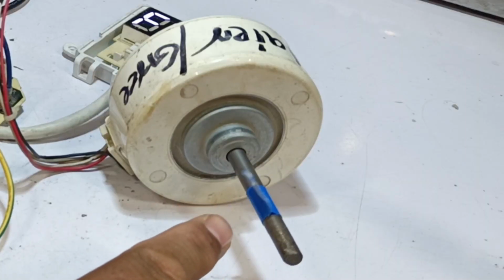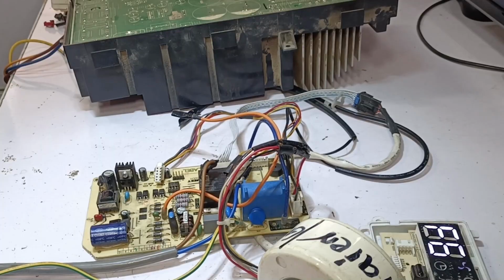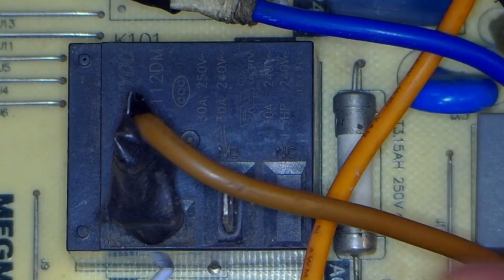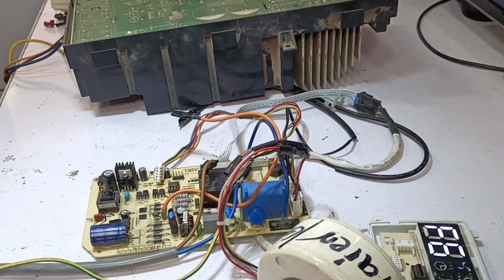Normally, the unit is installed above, and we don't understand why the F6 error is appearing. Sometimes we assume that the outdoor PCB is faulty or the wiring is damaged. Now look, as soon as the fan motor stopped, it started showing the F6 error. What's happening here is that the switching relay is not turning on under any circumstances. Someone has already worked on this PCB before, but the issue was not fixed. Now, since the relay is not turning on, it is not supplying power to the outdoor unit. And when the outdoor unit doesn't receive power, the F6 error is bound to appear.